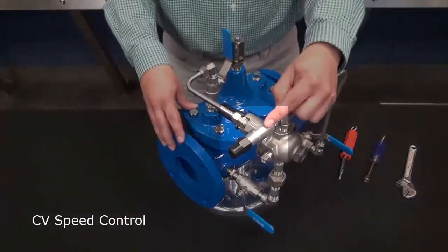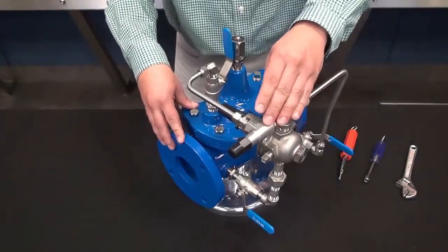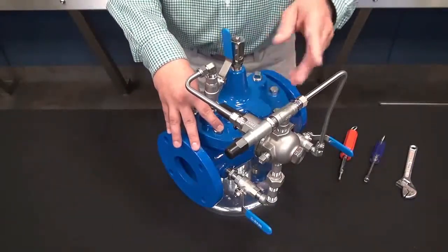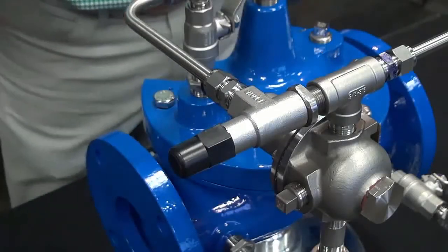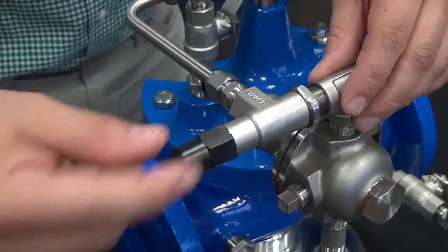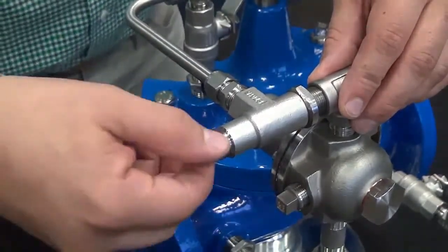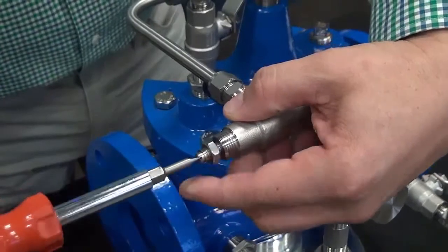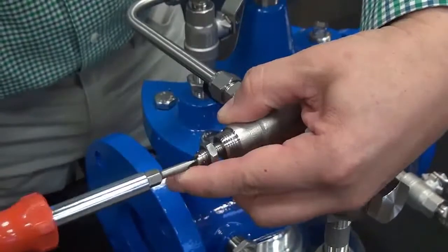Now our CV speed control — in this case here this is an opening speed control. Opening speed controls are standard on all valves 3 inch and smaller. On valves 4 inch and larger, opening and closing speed controls are both optional features. We want to make sure that the speed control is backed out and out of the way when we are setting this valve. So we remove the cover, loosen the jam nut, and back this out so that the speed control is out of the way.